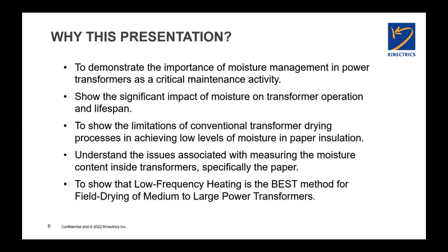We'll talk about issues associated with how we measure moisture inside transformers, because that is kind of germane to some of the misgivings and misconceptions that are out there. And just to leave you with a taste of all the methods that are available for drying transformers, that low frequency heating is by far the best method for field drying of medium to large power transformers.